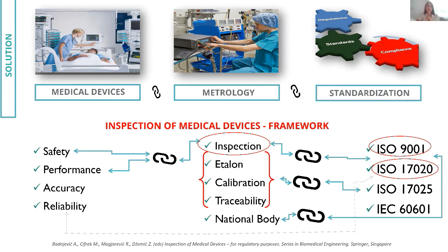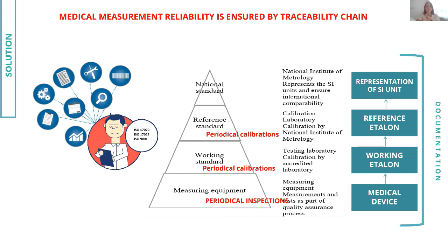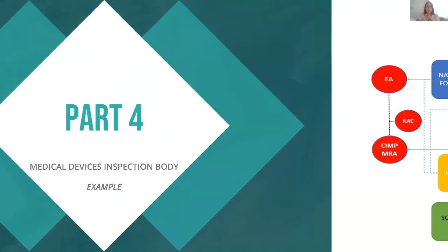More about this legal metrology framework has been published in a book by Springer, Inspection of Medical Devices. If you have access to this book, you can read more about the procedures for collection of data from defibrillators, anesthesia machines, ECG devices, infant incubators, etc. In this way, with this framework in action, we are able to ensure medical device measurement reliability as we keep the traceability chain in Bosnia and Herzegovina. So this is how it is linked together in Bosnia and Herzegovina.